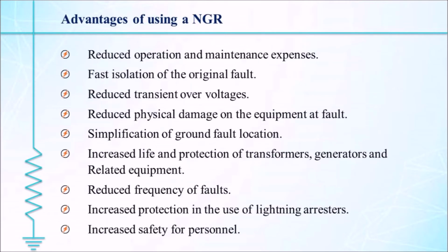This slide gives the advantages of using an NGR. First, reduced operation and maintenance expenses. Second, fast isolation of the original fault. Third, reduced transient voltages. Fourth, reduced physical damage to the equipment at fault. Fifth, simplification of ground fault location. Sixth, increased life and protection of transformers, generators and related equipment.